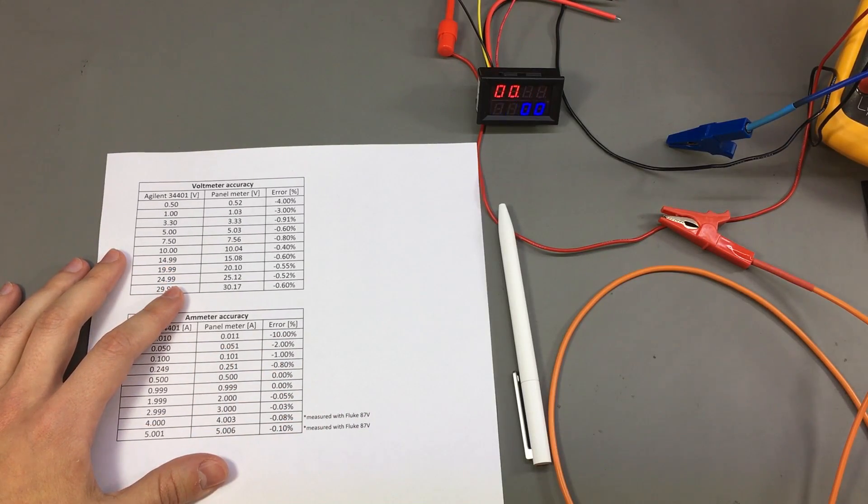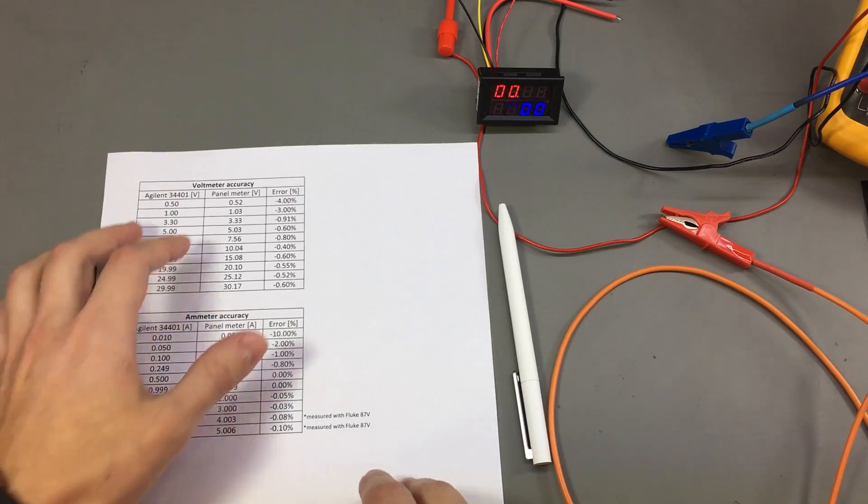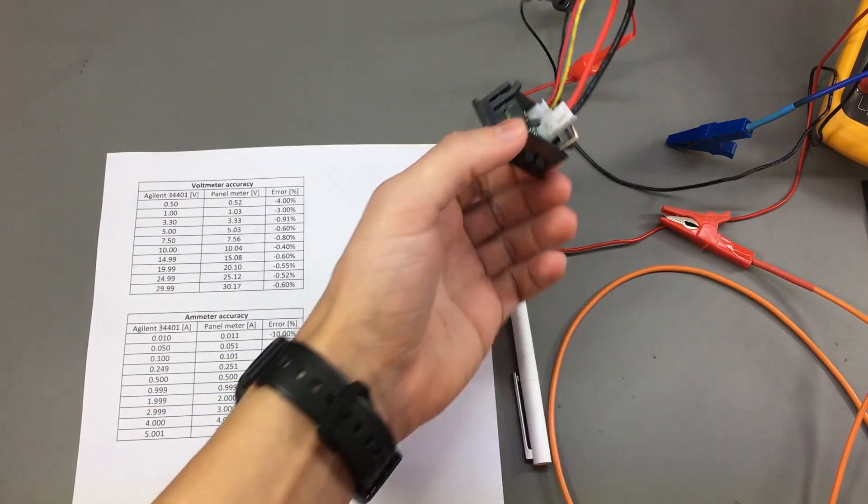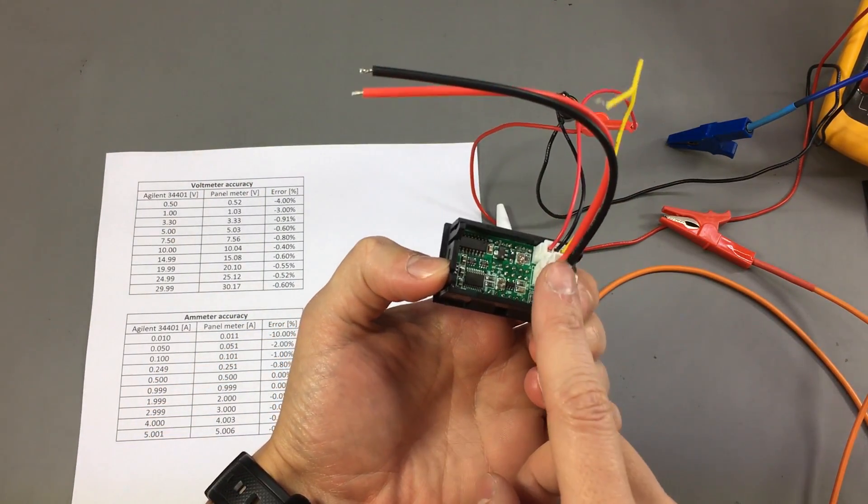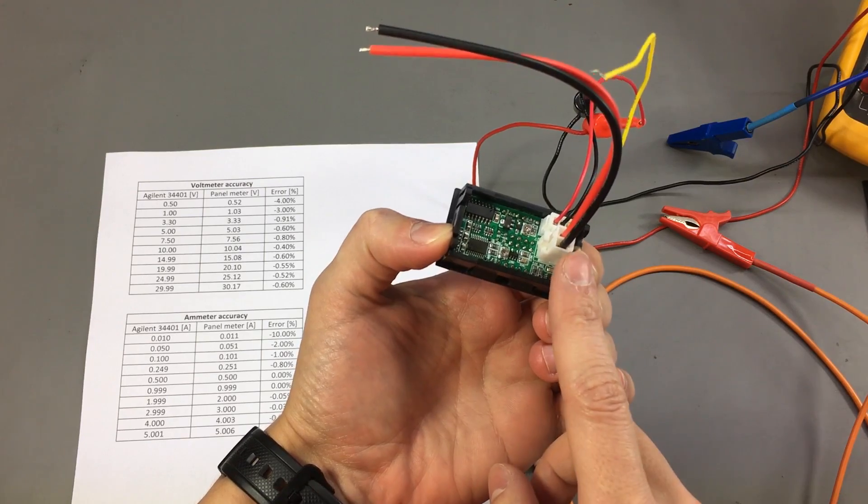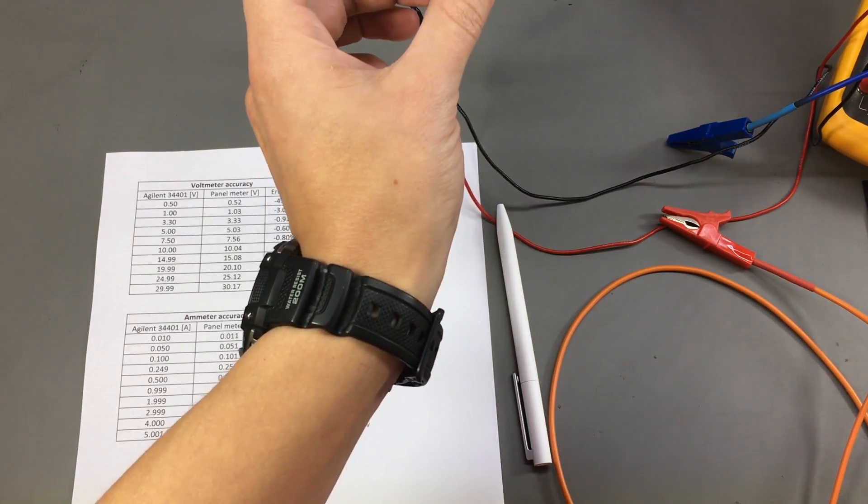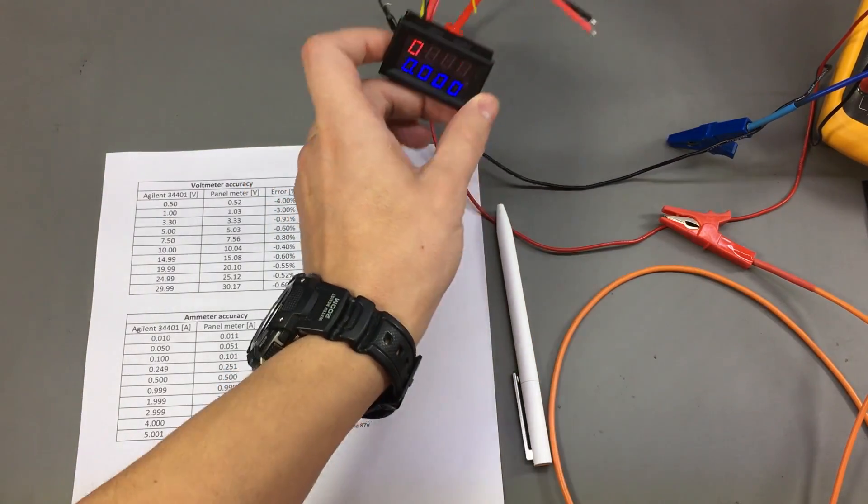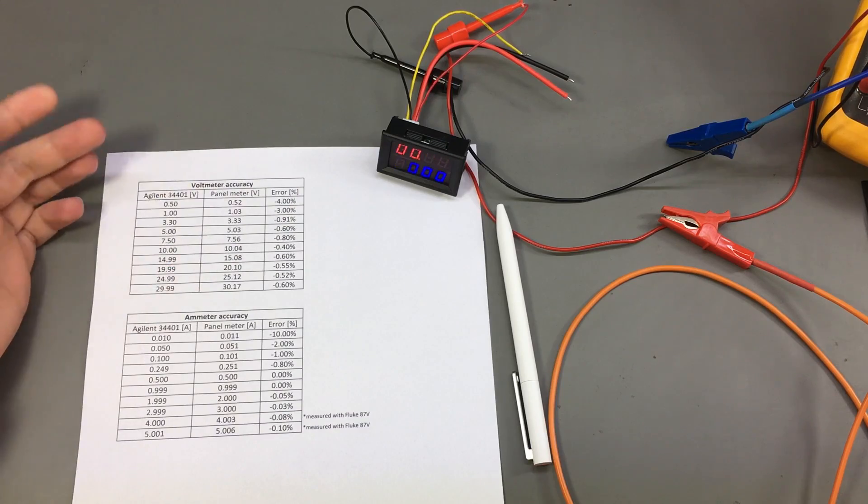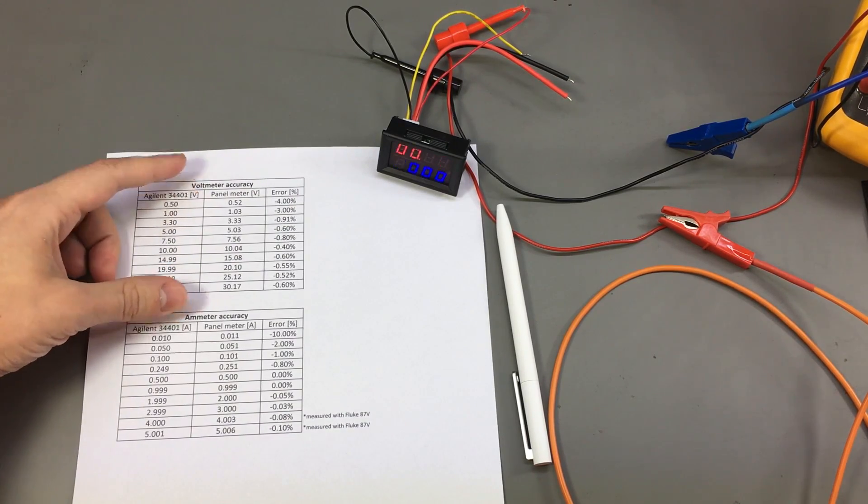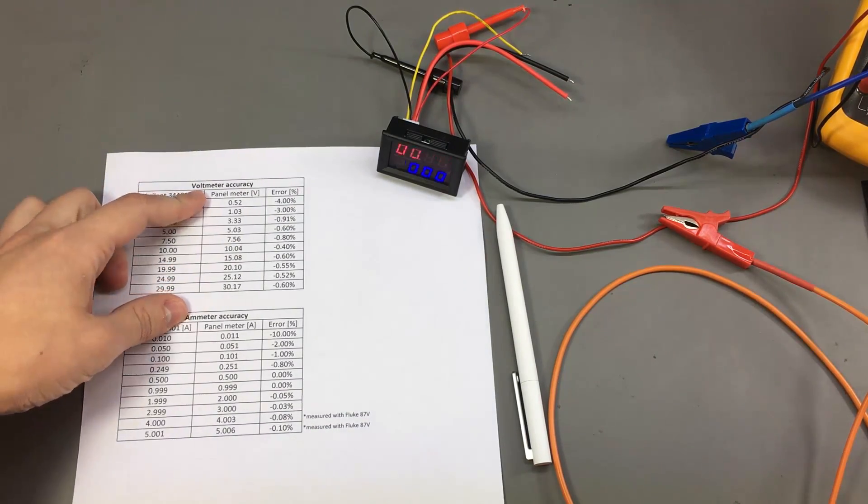Now what I would like to do is try and fiddle with the potentiometer on the back and see if I can adjust the voltmeter to fall within 0.08% at least for some part of its range like these measurement points that I used during my test.